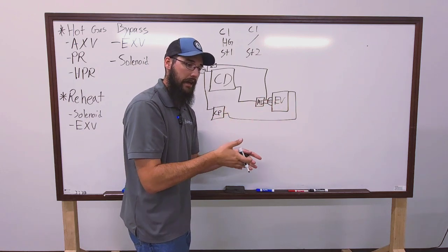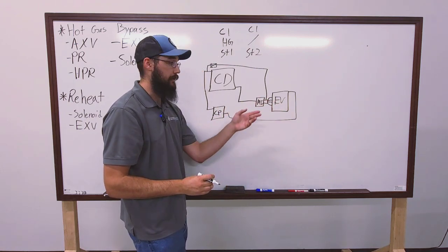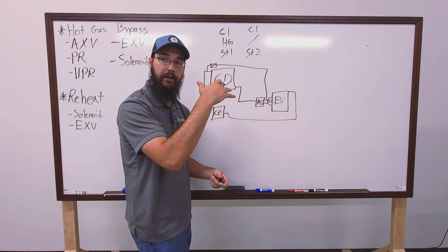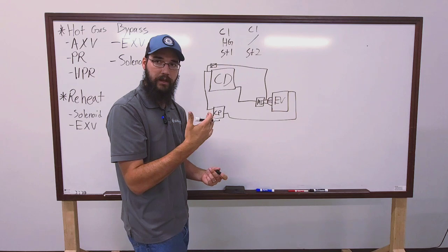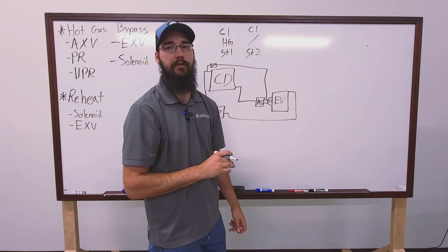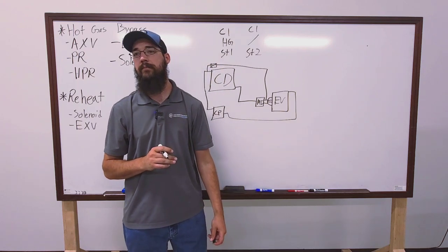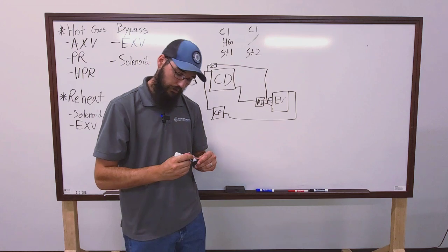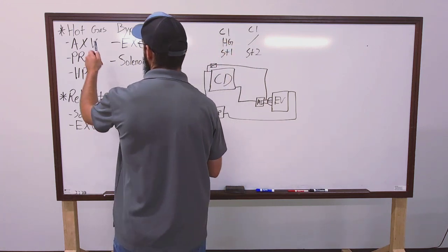So, we're not completely bypassing the coil. It is an intentional metered amount. It's not just a full-flow, no condenser at all. It's only intended to do just enough to keep your saturation high enough to maintain load. So, say you're getting down into the lower 30s on saturation, that bypass might bring you back up into the mid to upper 40s, sometimes, if it's oversized, maybe even into the 50s. Typically, if it's sized correctly, it won't be that extreme.